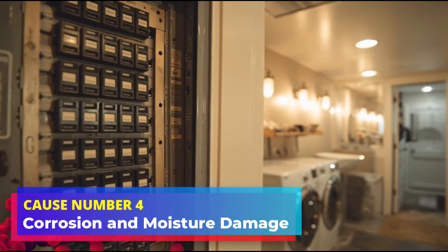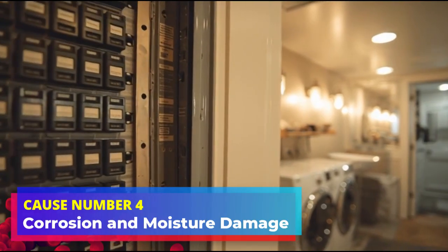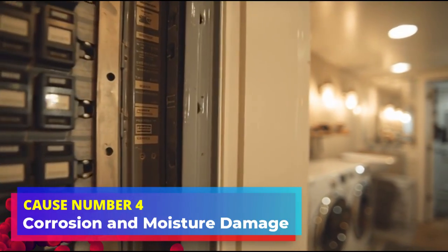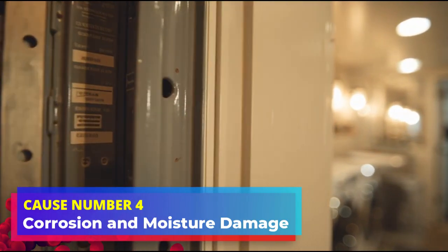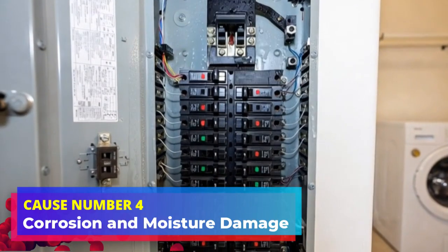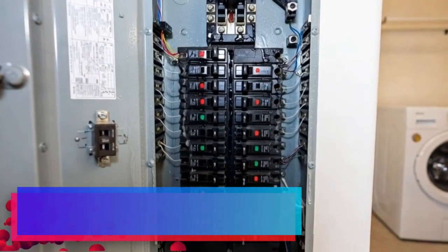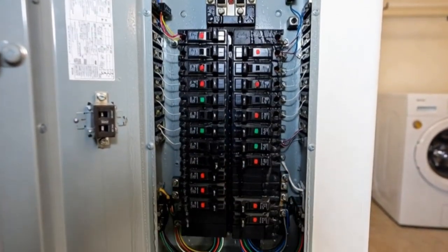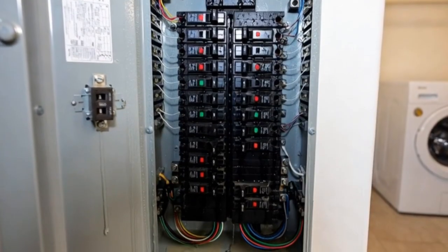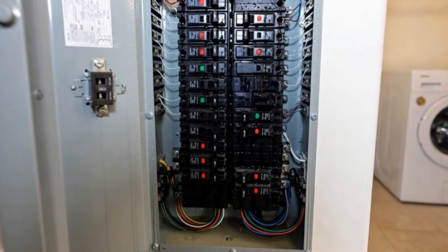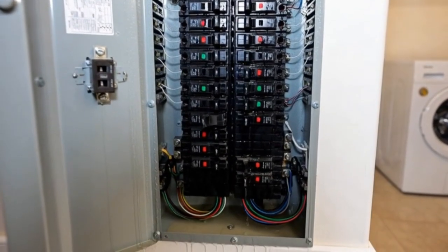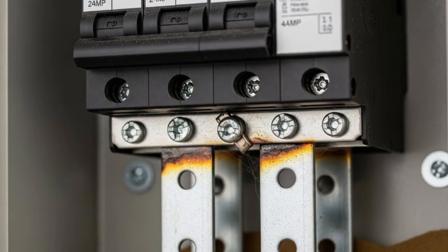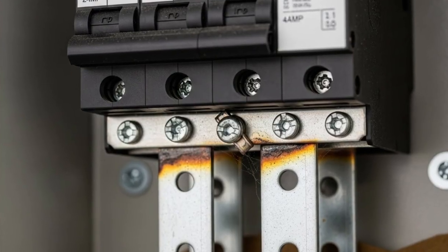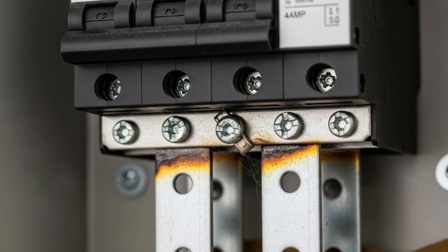Electrical panels installed in garages, basements, laundry rooms, and exterior locations face a common enemy: moisture. When moisture enters a panel, it causes corrosion on bus bars, breaker contacts, and wire terminations. Corroded connections increase resistance. Increased resistance generates heat. And as we discussed earlier, excess heat causes breakers to trip. But moisture causes another problem.